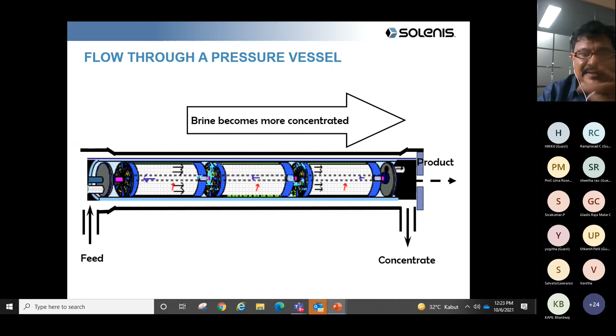This is called a pressure tube, which could be 4 elements long, and we call each membrane one element. Normally the size of the membrane is 8040, meaning 8-inch diameter and 40-inch long, or it could be 4-inch diameter and 20-inch long. So it could be a 4 element or a 6 element. And the percentage recovery is nothing but the permeate flow divided by the feed flow, times 100.